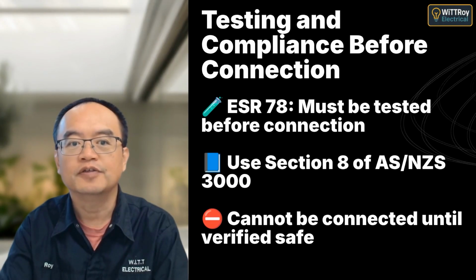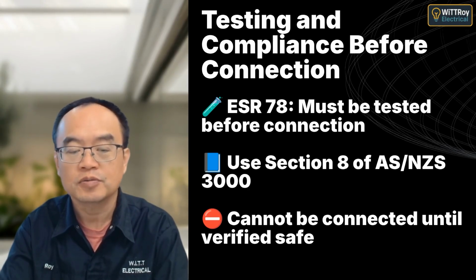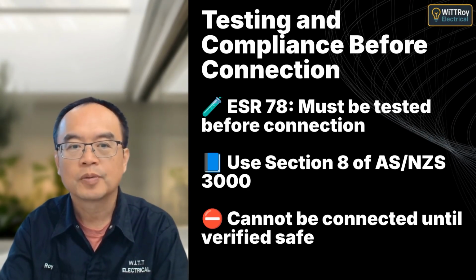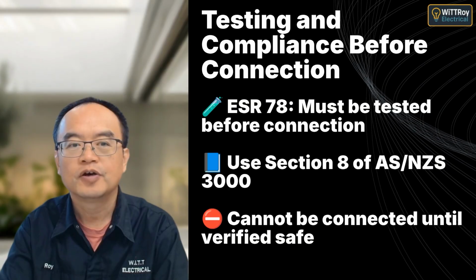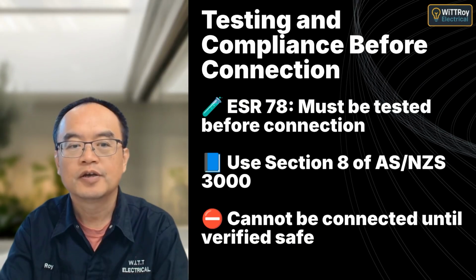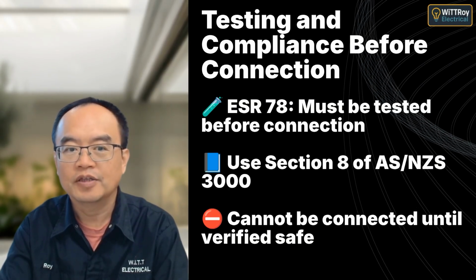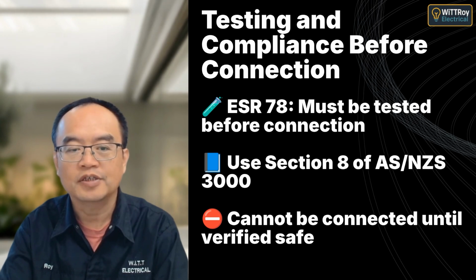Under ESR 78, a new connectable installation must be tested before it can be connected to a power supply. The testing must follow Section 8 of AS/NZS 3000. No connection is allowed unless the installation is confirmed to be electrically safe.